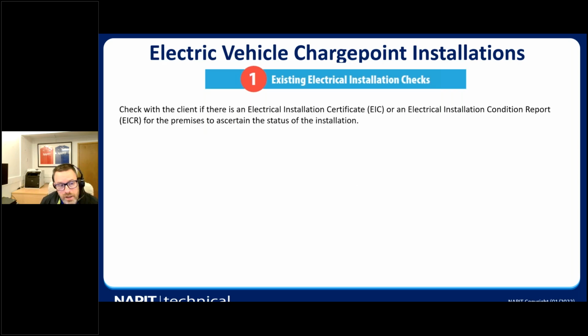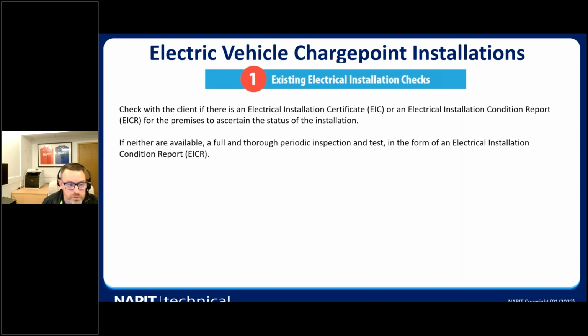So just check with the client if there's been a previous EIC or an EICR for the premises, and that will give you an indication of what the status of the installation is. So any problems that would be highlighted on either the certificate or the report would allow you to see what the problems are. If neither of these are available, then a full inspection and testing of the installation may be required in the form of an EICR to establish if there are any issues with the installation.